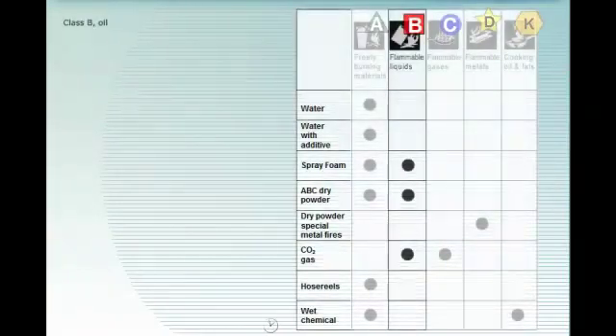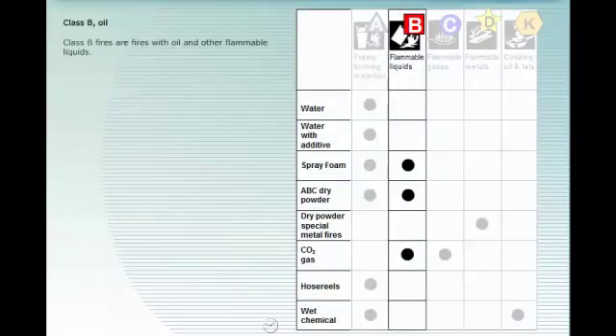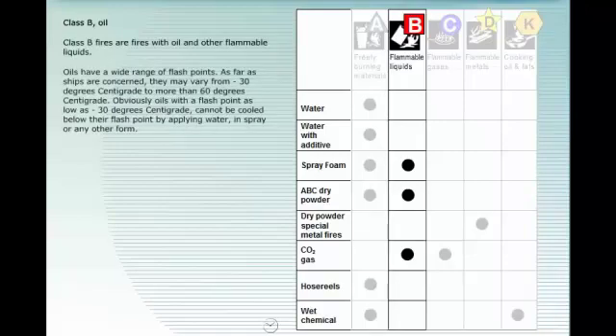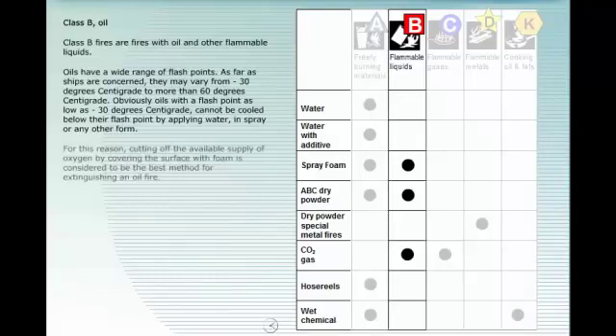Class B fires are fires with oil and other flammable liquids. Oils have a wide range of flash points. As far as ships are concerned, they may vary from minus thirty degrees centigrade to more than sixty degrees centigrade. Obviously, oils with a flash point as low as minus thirty degrees centigrade cannot be cooled below their flash point by applying water in spray or any other form. For this reason, cutting off the available supply of oxygen by covering the surface with foam is considered to be the best method for extinguishing an oil fire.